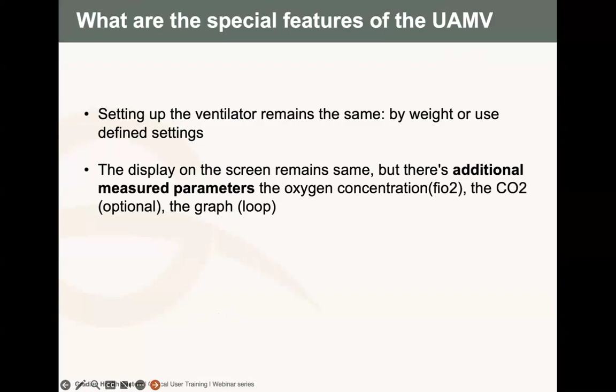So if this connection type makes the difference from the previous UMV, whereby we only had one pipe passing from the UAM to the ventilator. But at this time, we have two pipes connecting the ventilator to the UAM. So all fresh gas flow passes through the UMV, even if you are not using the ventilator, even if the patient is on spontaneous ventilation. And this means that on spontaneous or mechanical ventilation, we are going to analyze the tracing and everything on the screen of the UAMV. Even the FiO2 readings are still going to be measured on the same screen of the UMV.